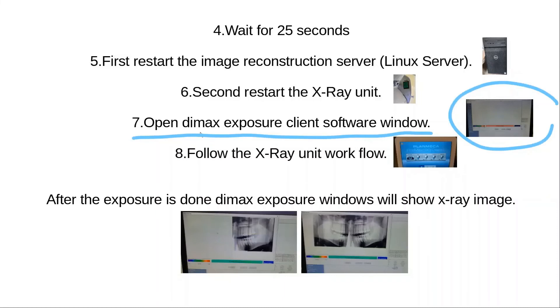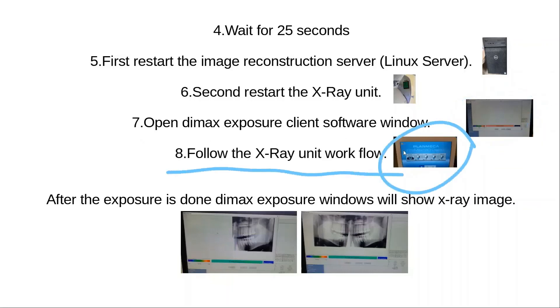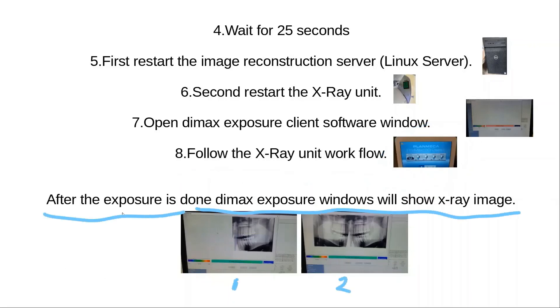Once done, move on to step 8: go to the X-ray machine, follow the prompts on the X-ray machine LCD screen, and follow your workflow. Once you start the exposure on the X-ray machine, you should see an image coming up on your Windows client software. You can see the progress as shown in these two pictures.